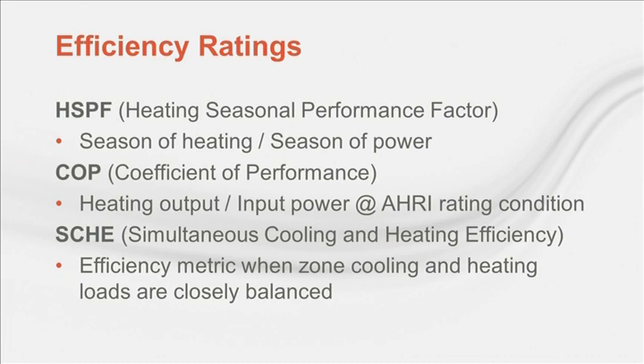SCHE depicts the efficiency of a heat recovery unit when operating at a condition where the zone cooling loads and heating loads are very closely balanced. Now, in real buildings, this condition is probably rare, since commercial buildings tend to be cooling dominant. So the usefulness of SCHE is really to compare VRF products to each other to see how efficiently they actually do simultaneous heating and cooling.